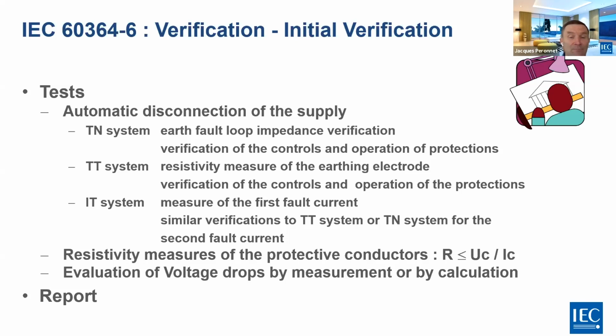The resistance measure of the protective conductor also is key. You are going to verify it. And you are going also to make an evaluation of the voltage drop by measurement or by calculation. I remind you also that voltage drop is a key element for energy efficiency in your installation, not only for safety, but also for energy efficiency.